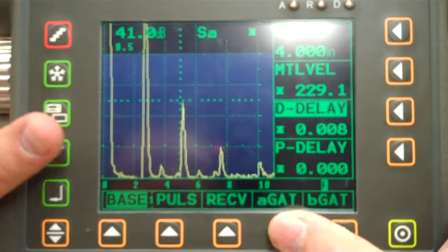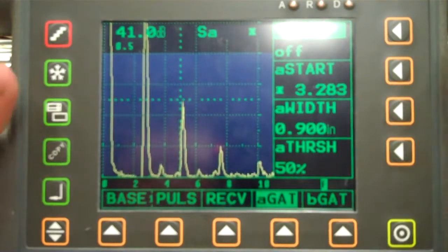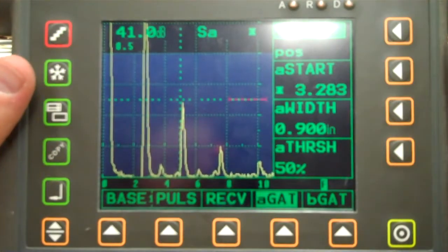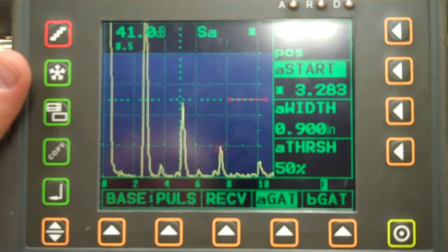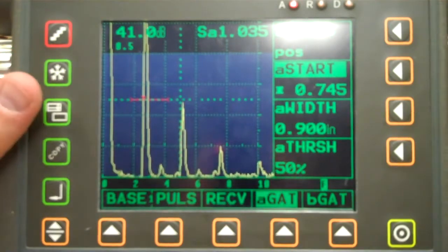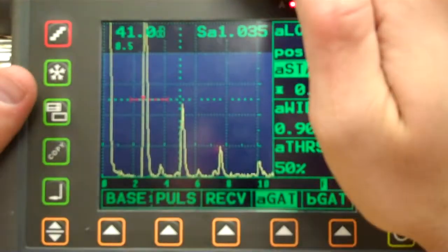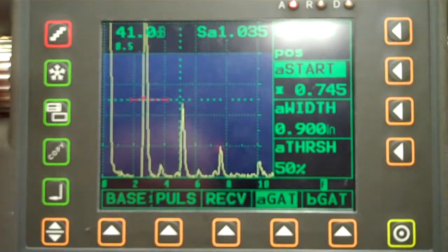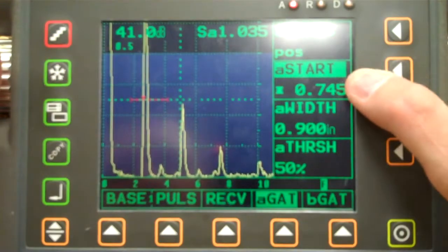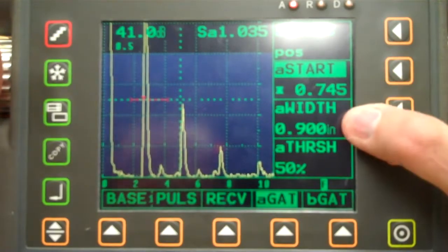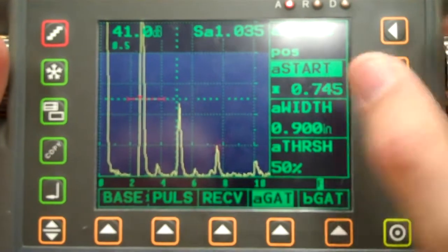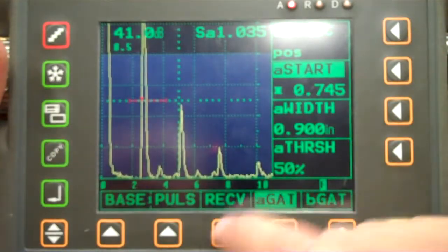Now, let's bring a gate into the equation. Okay, and a gate is just that electronic signal. So I'm going to turn the gate on. That's a positive gate, that's a negative gate. They look the same. That's okay, so I'm going to leave it on a positive gate. I'm just going to gate start, meaning I'm just going to move this thing. Okay, I'm just moving it. Now, we see here that our signal, it's popping up here, SA, is telling us it's right at 1.035 inches. Okay, I have a gate start of basically 3/4 of an inch, gate width of 9/10 of an inch, and then the threshold's right at 50%. Okay, so I'm going to leave that over there.